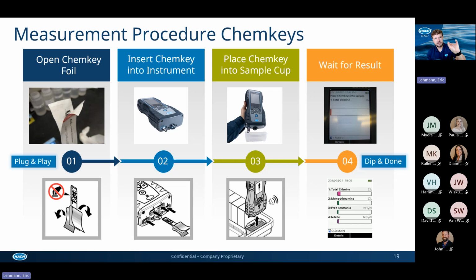So I have my packet of Chemkeys right here. This one happens to be total hardness low range. I'm going to take that out of the packet. Here's my Chemkey. I'm going to place that into the bottom of the instrument. We have 4 ports. Let's put that into the first port. That's my low range total hardness. Maybe I want to do an alkalinity test. So let's do an alkalinity Chemkey. I'll put that into the second port, like that. So now we have one in the first port and the second port.